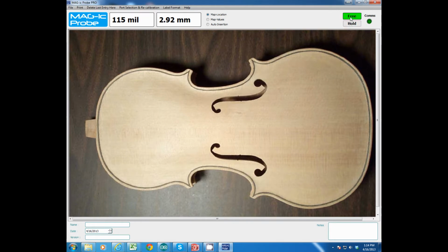There is a free and a hold mode button at the top here, which can be engaged. What this means is that when I'm doing a measurement and I press the hold mode, no larger measurements will be allowed through to update the display. Only smaller measurements will be allowed through. So when I decrease the measurement, it'll hold the lowest value. When I now move the magnet on the probe, nothing will increase. It'll only allow smaller measurements to go through, and I can get back to my normal mode by unclicking the free mode again. That allows you to get the lowest possible measurement at a particular location, to make sure that your probe is vertical and that the ball is centered on the probe at the bottom of the instrument.